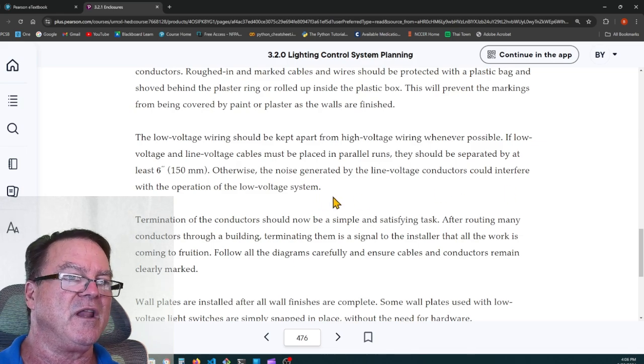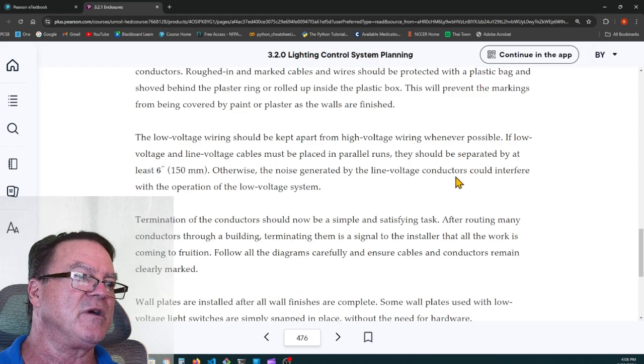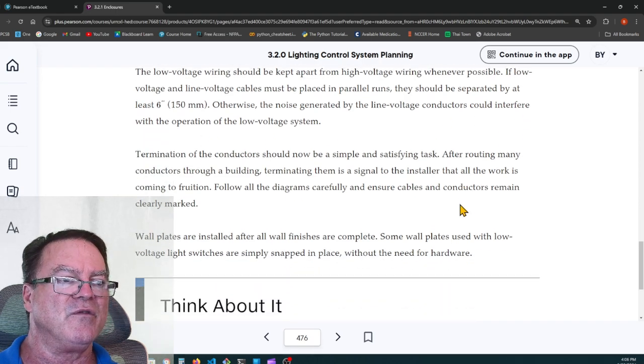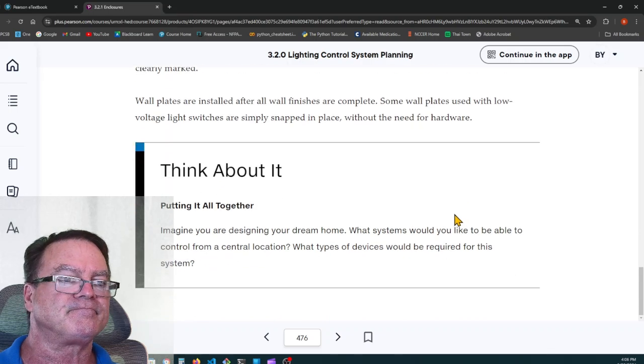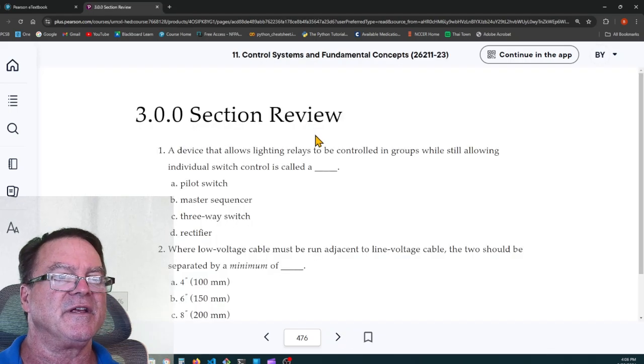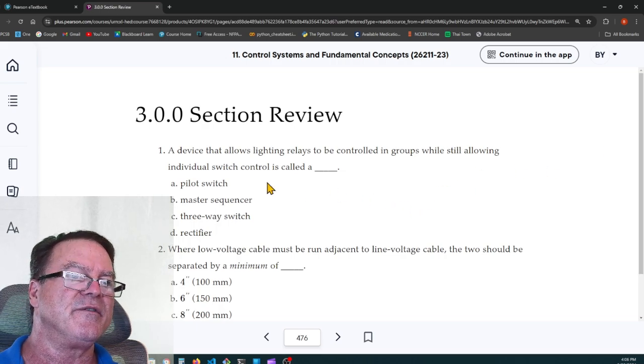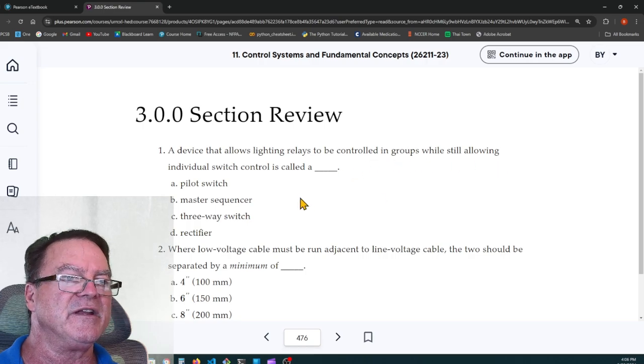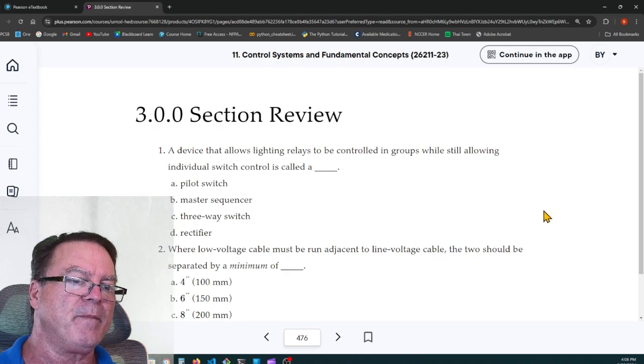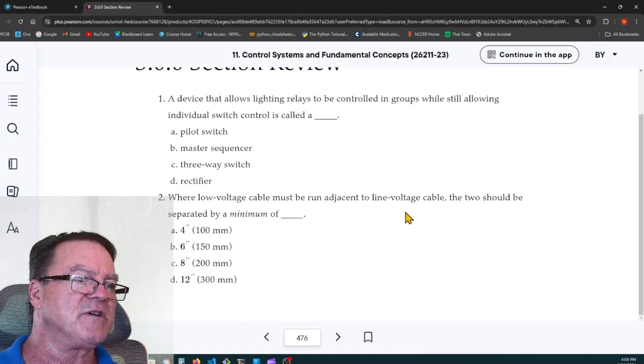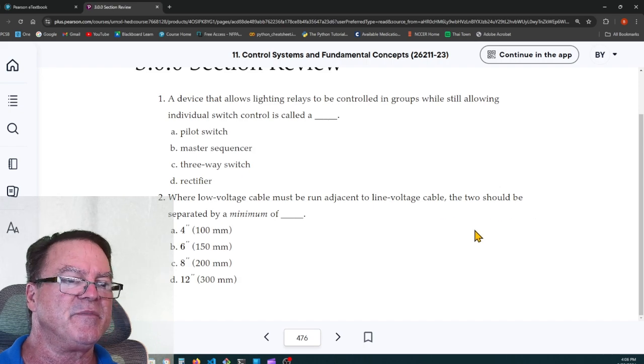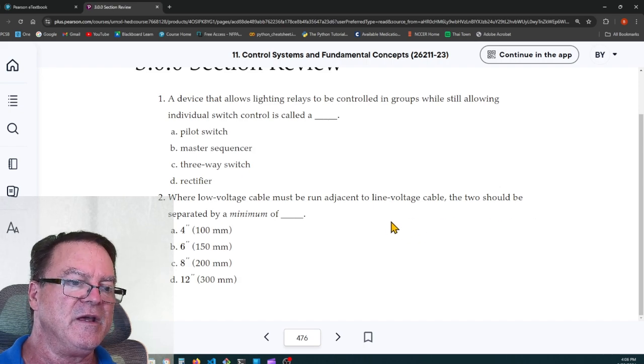If low voltage and line voltage cables must be placed in parallel runs, they should be separated by at least 6 inches. Otherwise, the noise generated by the line voltage conductors could interfere with the operation of the low voltage system. All right. So they're saying you might have some induced currents in the low voltage wiring. Section 3 review: a device that allows lighting relays to be controlled in groups while still allowing individual switch control is called a what? And where low voltage cables must be run adjacent to line voltage cables, the two should be separated by a minimum of how many inches?